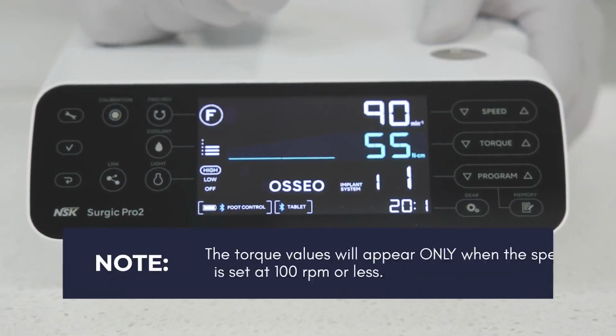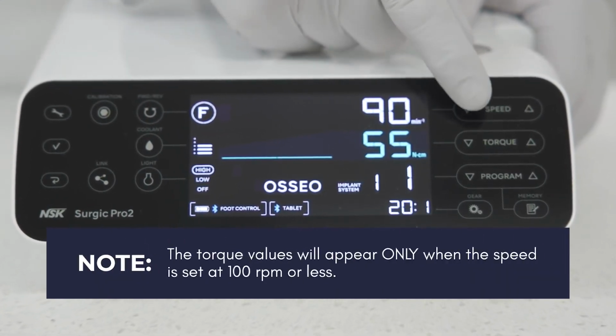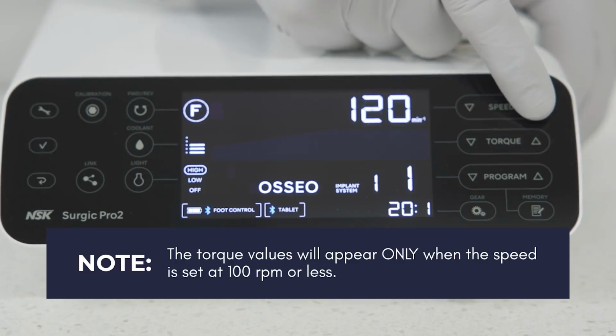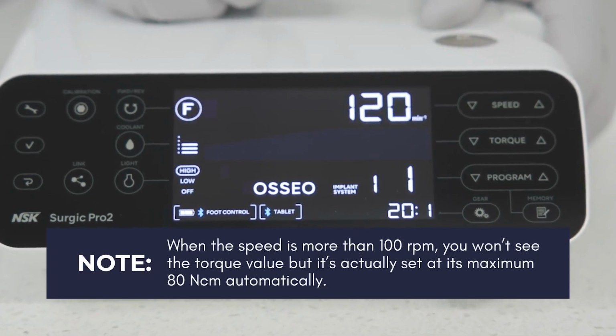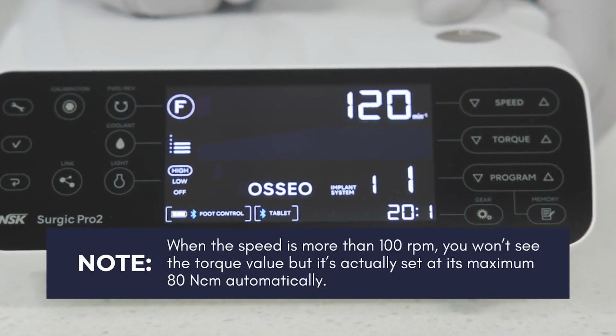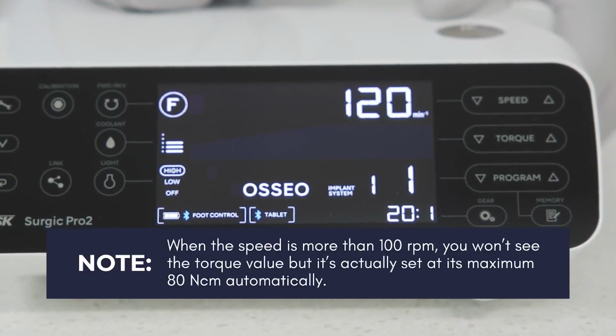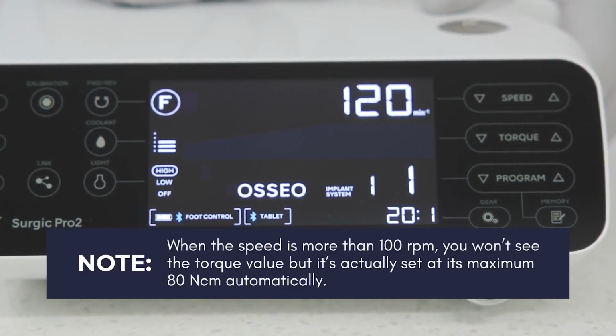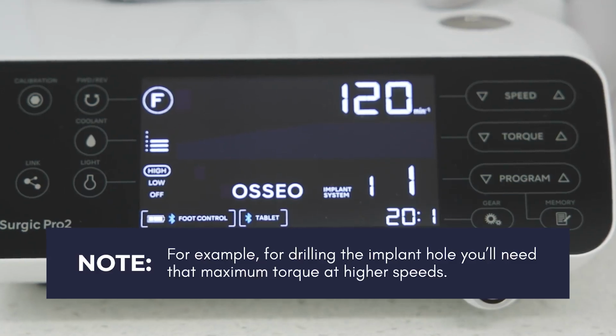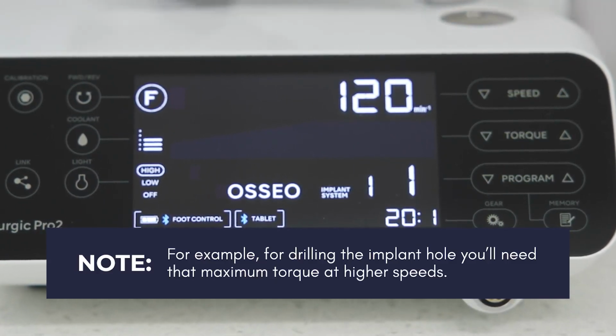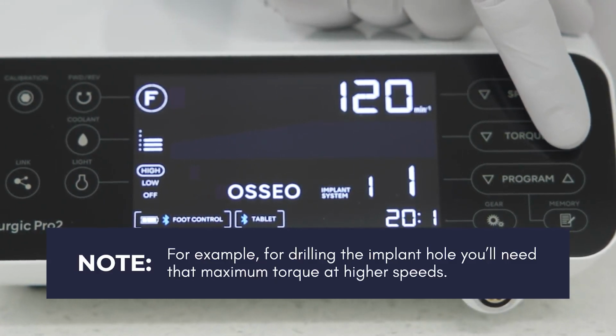Note: the torque values will appear only when the speed is set at 100 RPM or less. When the speed is more than 100 RPM, you won't see the torque value, but it's actually set at its maximum 80 Newton-centimeters automatically. For example, for drilling the implant hole, you'll need that maximum torque at higher speeds.